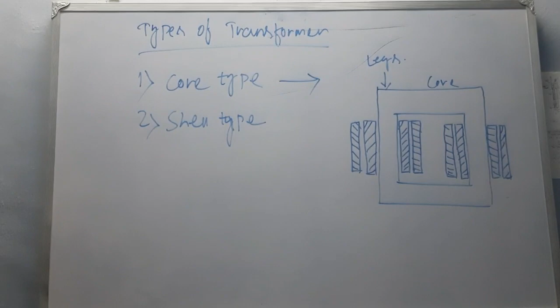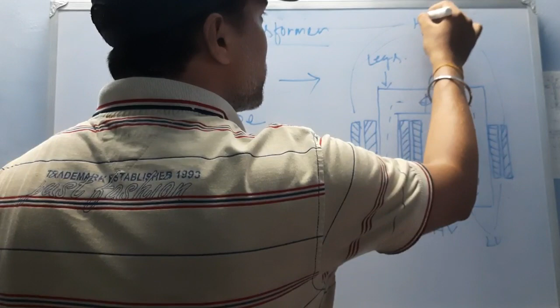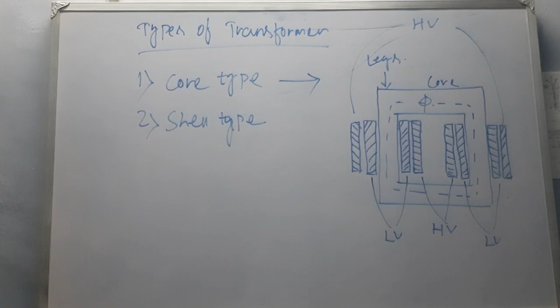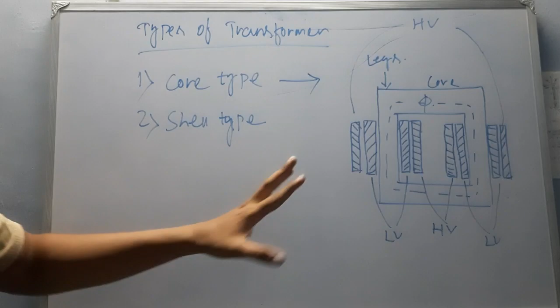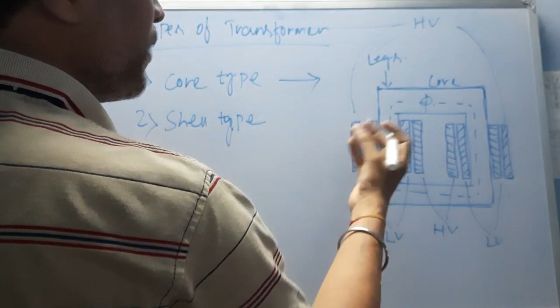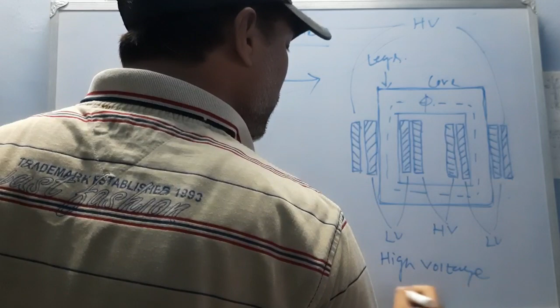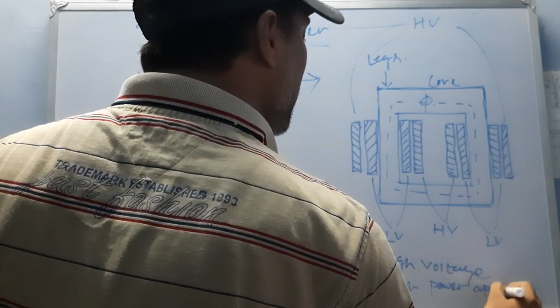Okay, these are its HV winding. HV, that means high voltage winding. It's outer of the low voltage winding, and these two are LV. Here these two are LV, and these outer windings are HV. You can see from this diagram. Actually, here the winding covers the entire core. This one is the core. Here this one is the core. This entire core is surrounded by the winding. That's why it is called core type of transformer. It is generally used for high voltage and high power application.